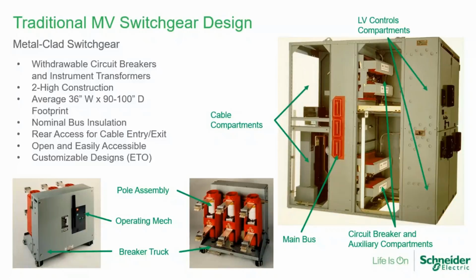You have a nominal bus insulation, basically an electrocution barrier coating around the main busing of the switchgear, that is required by the metal-clad standard. But I think the key thing to keep in mind here is that the dielectric ratings, the dielectric calculations, are all done using air gap, as opposed to using that nominal insulator around the main busing. It requires both front and rear access for where the cable entry is going to be. A very open and easily accessible design, and a very customizable design. And this is good in the sense that if you need to be able to bus up to existing switchgear or do some custom busing entry applications, metal clad is probably the best option for you.